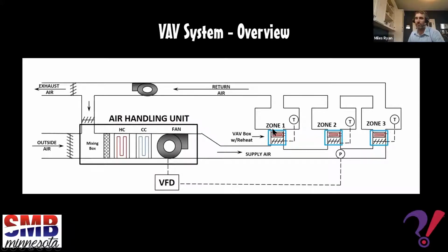The VAV box has 2 major components in it in this case. It's got a modulating damper, which can modulate to maintain the active airflow set point for that space. And it's also got a reheat coil, which can raise the temperature of that supply air going into that space if need be. So if it's calling for more cooling, we want to increase the quantity of that 55-degree air that's being sent into the space. The airflow set point would increase, and the damper would respond by opening a bit more. Okay, so that's zone 1. It's calling for cooling, and it's actively trying to control for cooling.